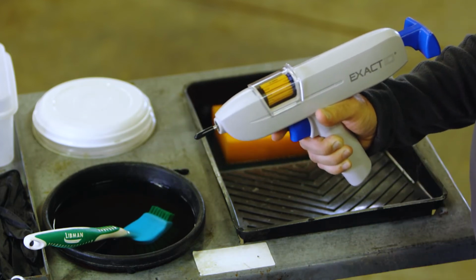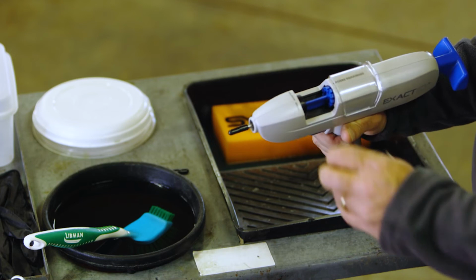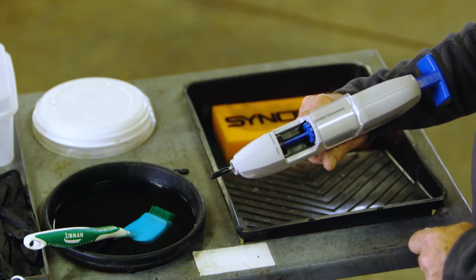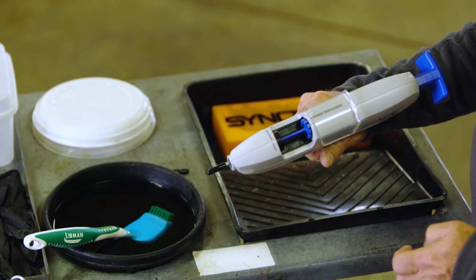To remove a clip, slide open the clip cover away from the needle. If needed, rotate the clip so that the zero is aligned with the dose's remaining arrow. If the device is cocked, then the applicator must be fired in order to rotate the clip to zero. Then, lift and remove the clip from the applicator.